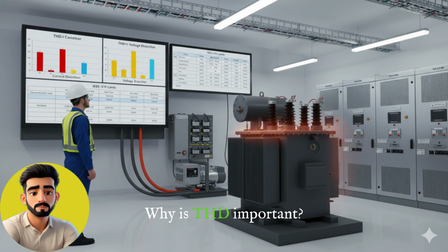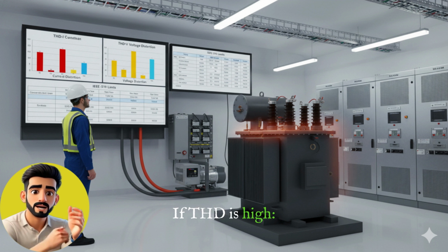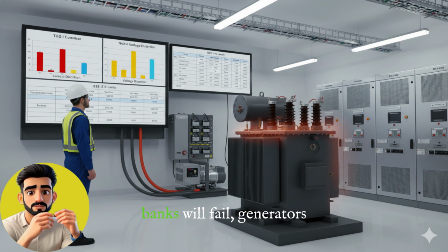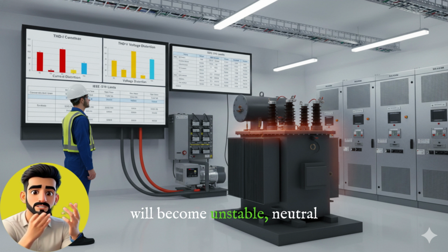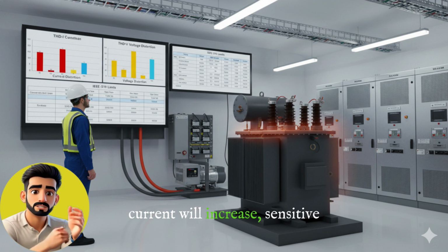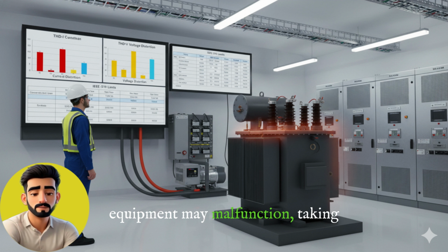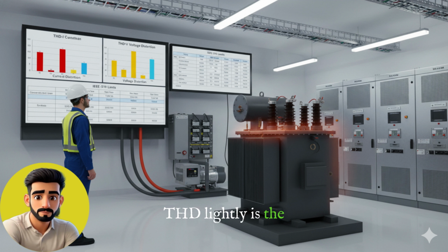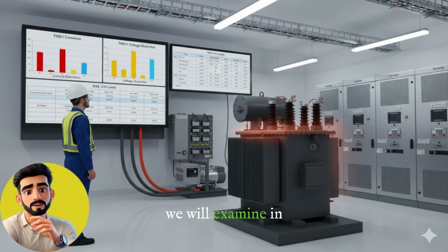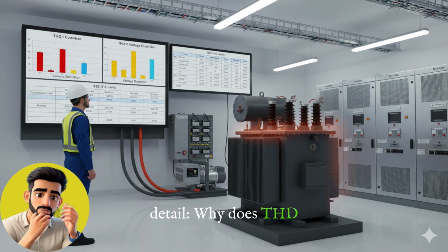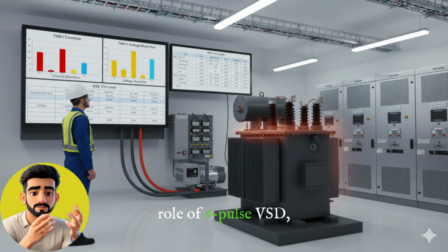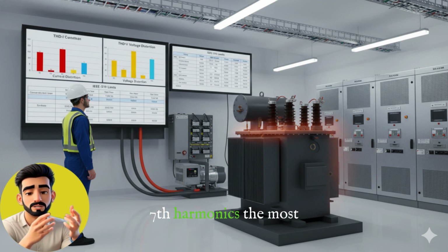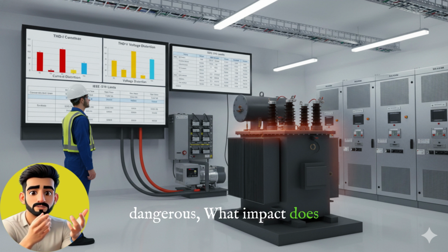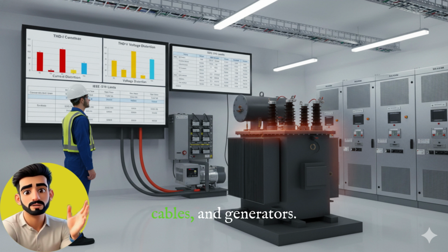Why is THD important? If THD is high, transformers will heat up, cables will derate, capacitor banks will fail, generators will become unstable, neutral current will increase, sensitive equipment may malfunction. Taking THD lightly is the biggest mistake. What will we see in this episode? In the upcoming scenes, we will examine in detail. Why does THD occur? What is the role of 6-pulse VSD? Why are 5th and 7th harmonics the most dangerous? What impact does THD have on transformers, cables, and generators?